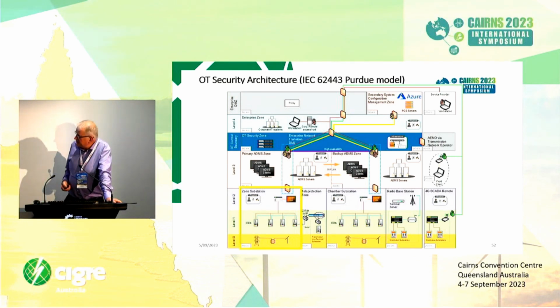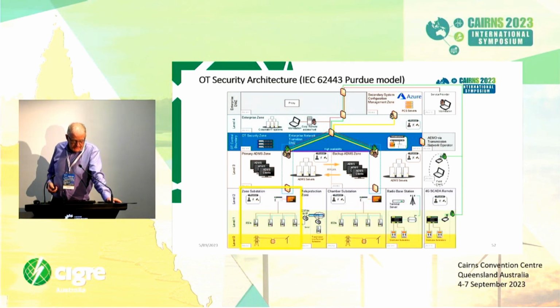So we've got substations, and we've divided the substations into three zones. There's a supervisory level zone that has all the SCADA equipment and interfaces to the protection relays. We've got a process level zone, which, in 61850 speak, is all the sampled values and GOOSE messaging in the station between devices. Then we've got the physical infrastructure itself, the electrical network down the bottom in that level 0.